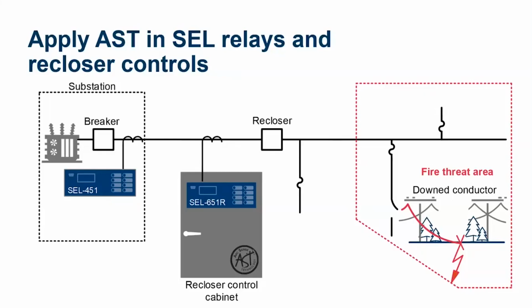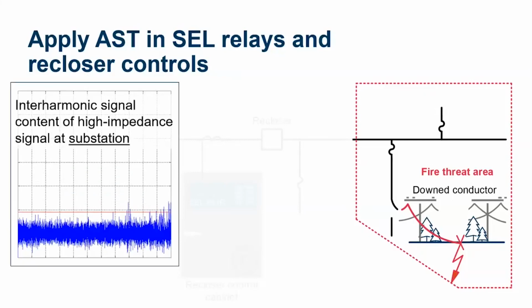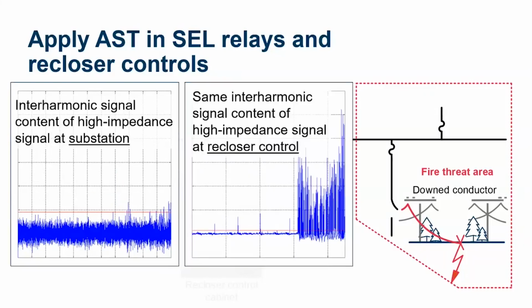So for this example here, where we see a high impedance fault further down the line, we may see this signature at the substation. Whereas if we were closer to the high impedance fault, at say the 651R recloser control, this is the signature that we might see. Being closer to the high impedance fault allows us to be more sensitive and also to detect that fault faster. So it's definitely recommended, in order to increase the sensitivity for high impedance fault detection, to deploy this technology at multiple locations within the power system.